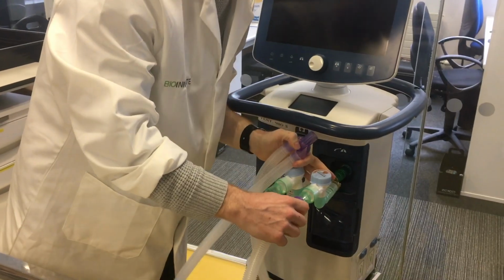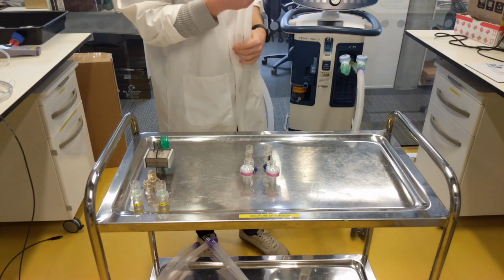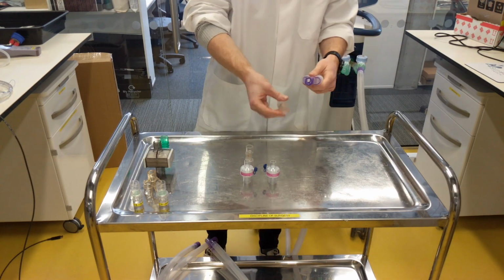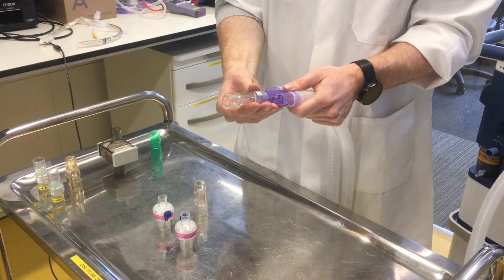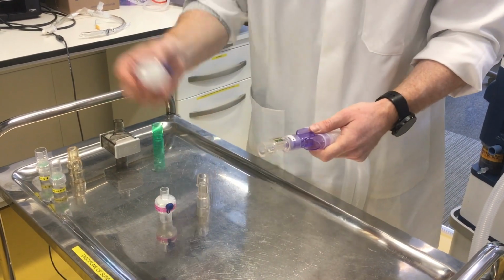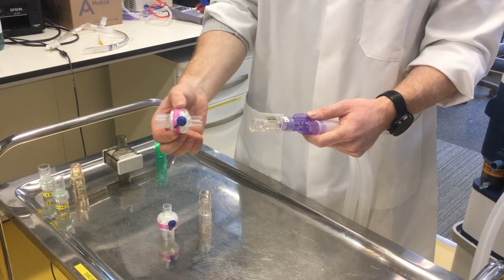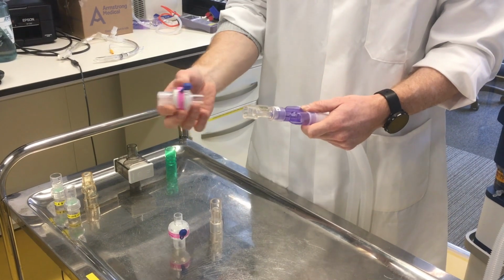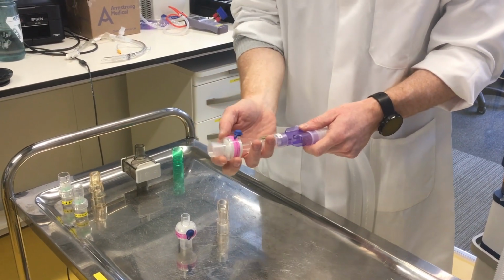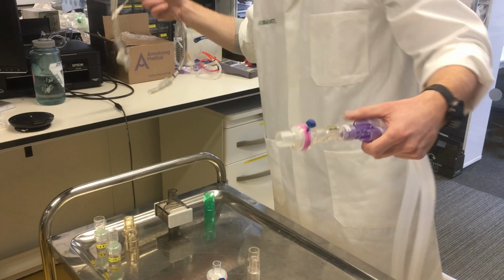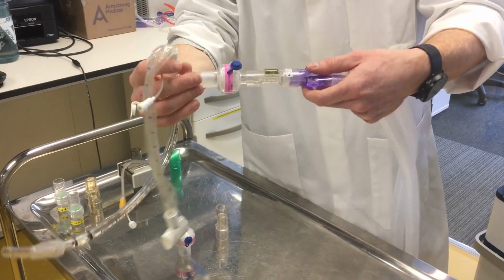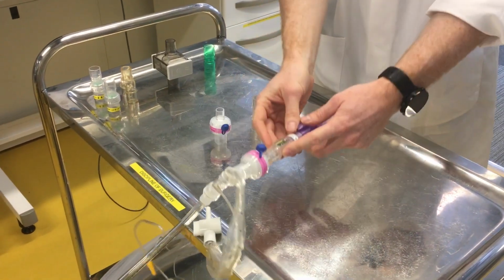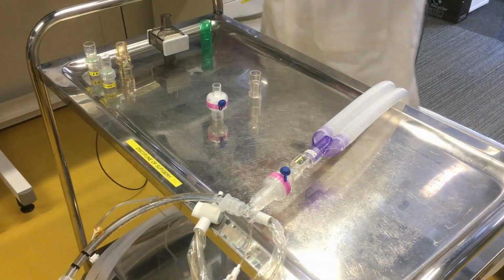We'll run one of the arms as the inspiratory limb for our first patient. That is going to run through to a flow meter, which comes right before the patient's mouth. We are in this case using an HME filter that's rated for bacterial and viral in order to prevent any contamination between patients. So that will attach right there, and that goes in as per your standard practice onto the ET tube.